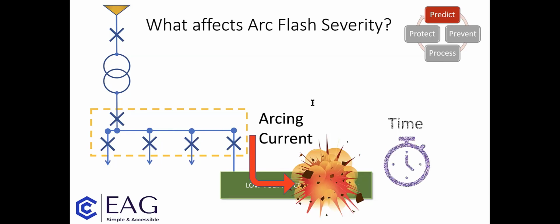And the other thing is time. So how quickly you can disconnect an arcing fault determines the amount of damage that's going to be done to your equipment for a start, but also to those nearby as well. And again, that's a direct relationship between time and the amount of incident energy. So if you've got a disconnection time of, I don't know, 100 milliseconds, if you can cut it down to 50 milliseconds, you will halve the amount of incident energy.